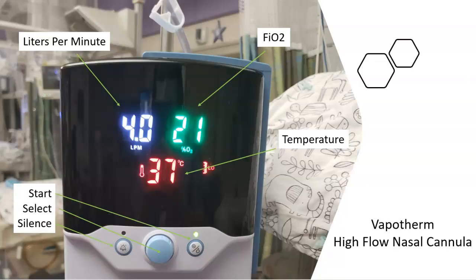This is the Vapotherm. It's a good piece of equipment. Over here we have our liters per minute, our FiO2, and our temperature. And really, all that changes between this one and the adult is the inner cartridge, so that it can be programmed for whether it be neonatal or for adult. So the neonatal will go from 1 to 8 liters per minute, and it will go up by half. So you can have like 3, 3.5, 4, 4.5.